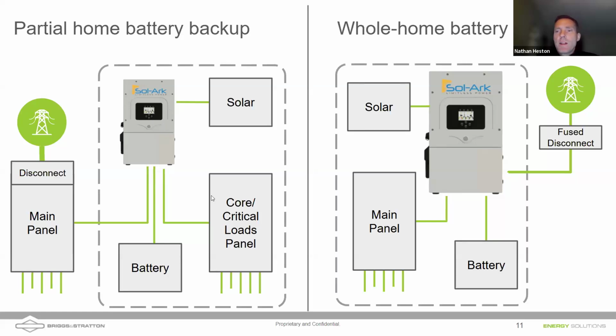Well, look at the difference on the right side of the screen. You're showing the whole home. Actually, showing the 12K inverter there, but meant to show the 15K. This is a whole home backup example in which we've got power coming from the main grid, and in a grid outage, the inverter isolates itself from the grid. But notice that the entire main load center of the house is backed up.